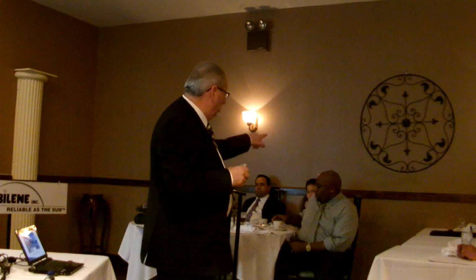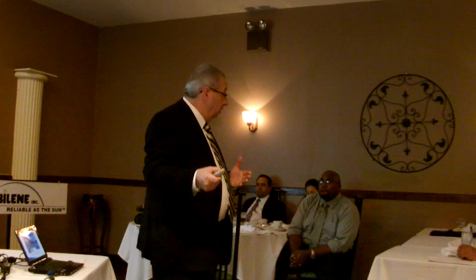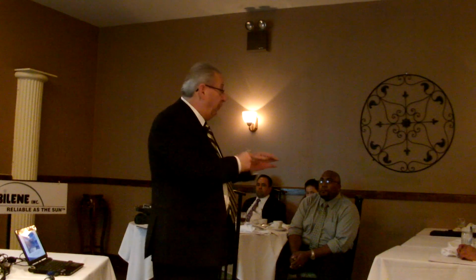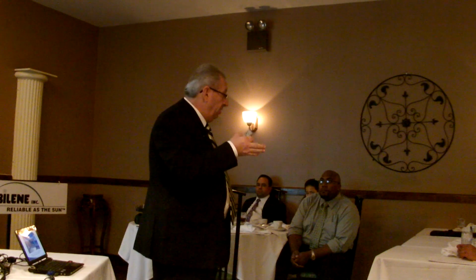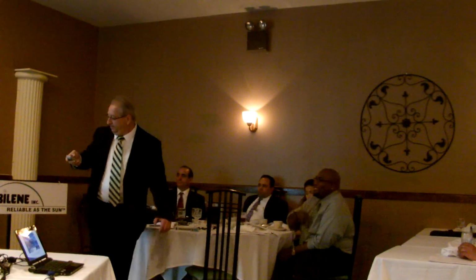That's why they need an extension to put on the chimney in order to accommodate this rule, because you really cannot move the building or the chimney. So, foreman, do you understand? 10 feet to the center of the chimney, 3 feet higher. You're going to remember this picture forever. Okay.